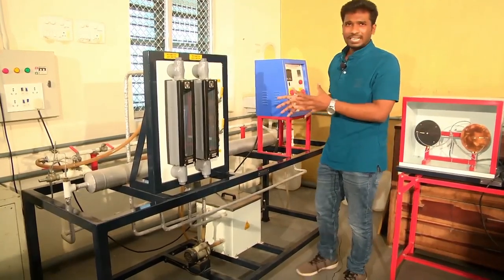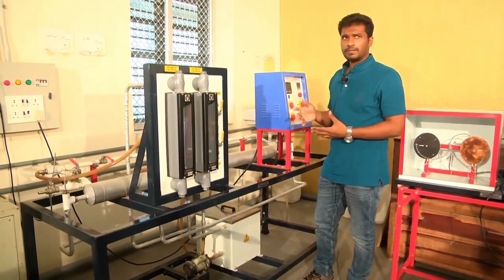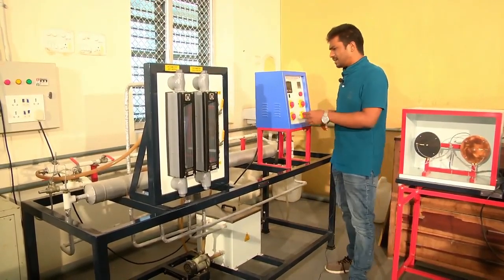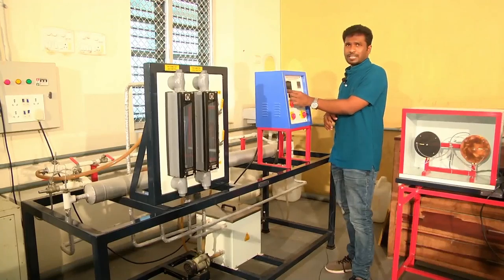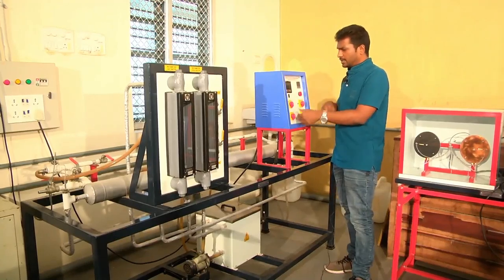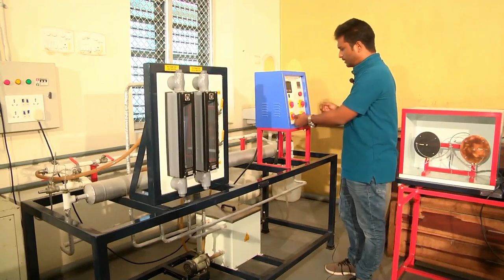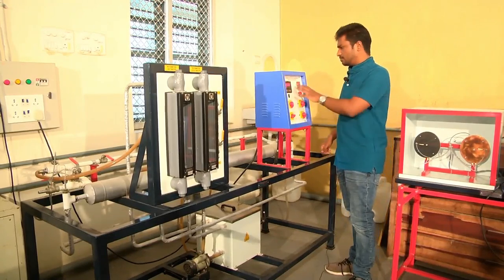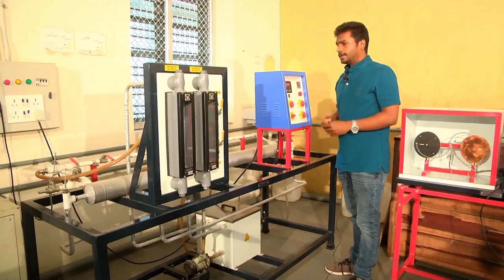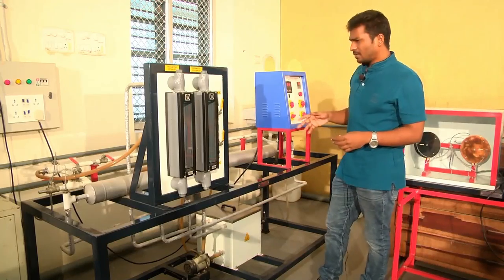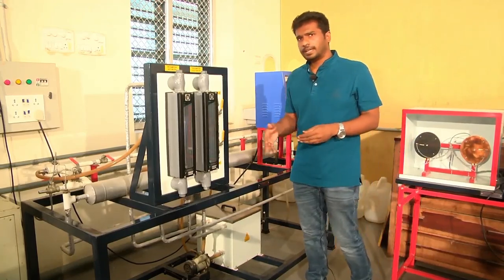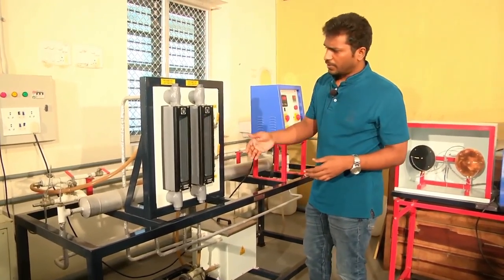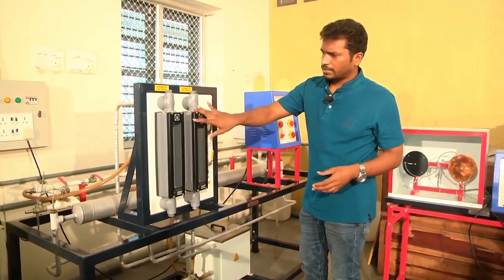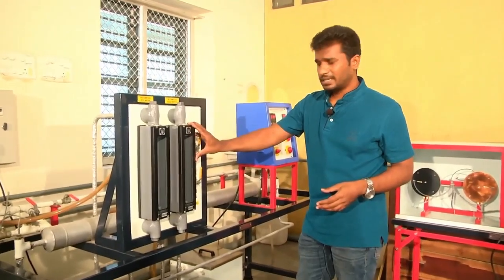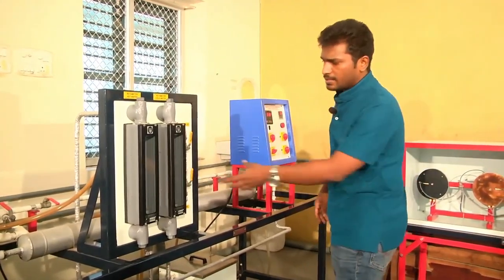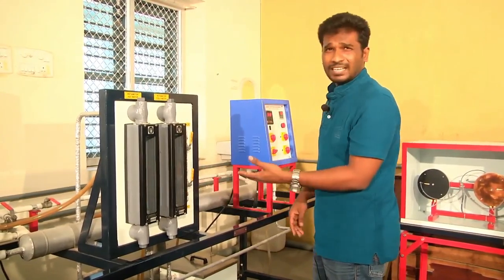The temperatures at the inlet and outlet of each fluid, hot water and cold fluid, can be seen through this temperature indicator. This is the temperature indicator, and this whole setup is powered up using this main switch. Now it has powered up, and the flow rates of hot water and cold water can be measured using these rotameters. The unit is LPH, liters per hour, and each has a bob which rises with the flow rate.